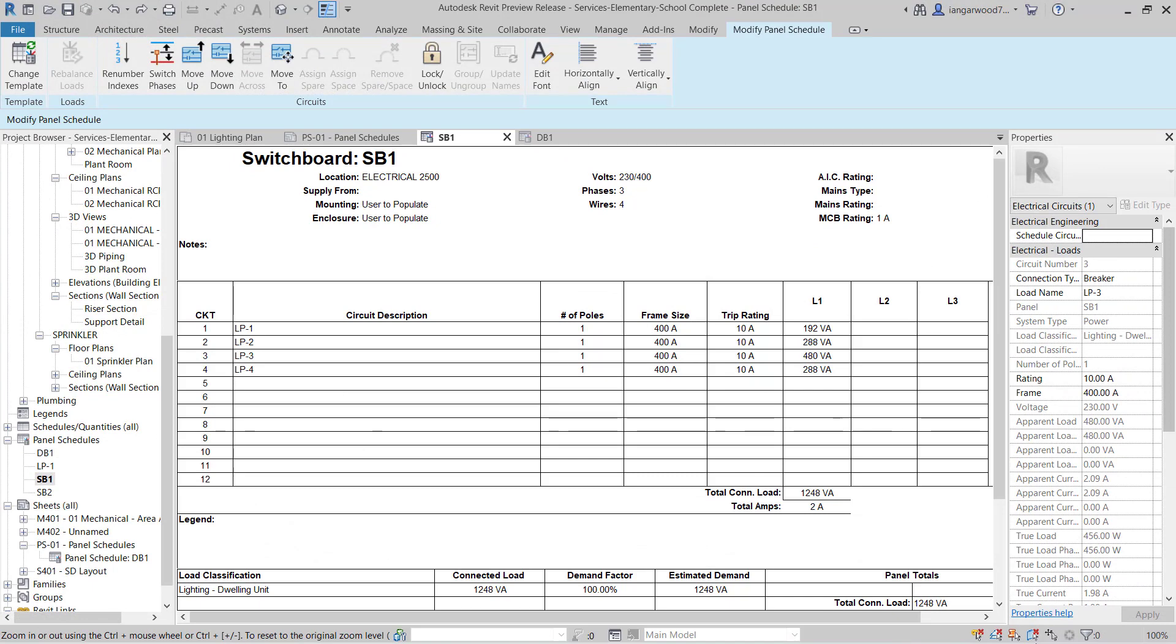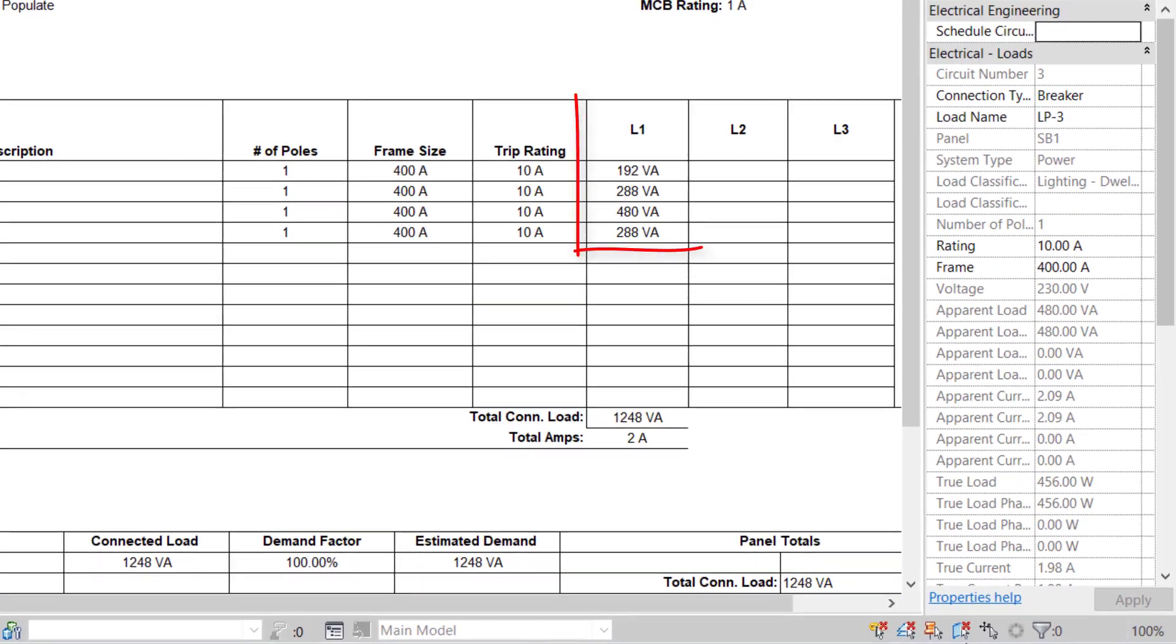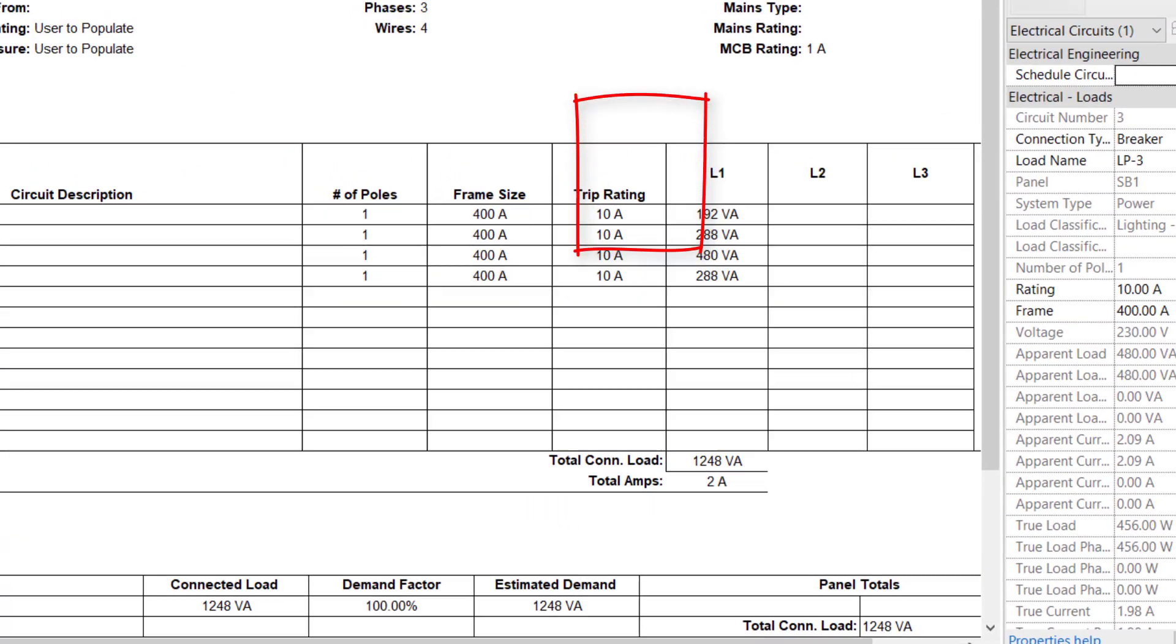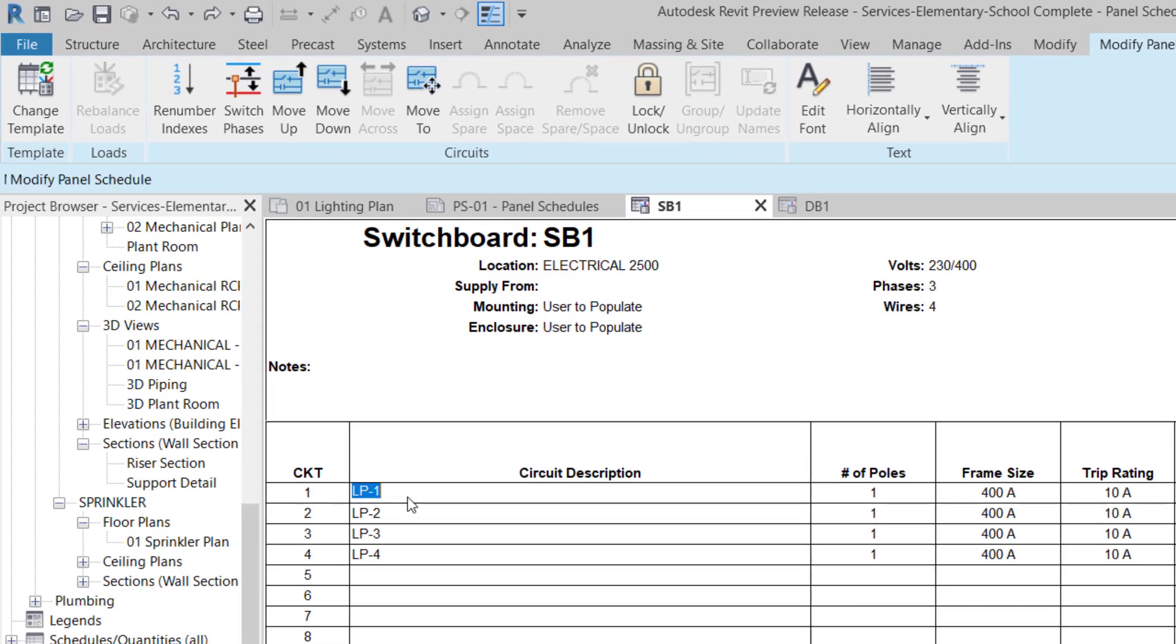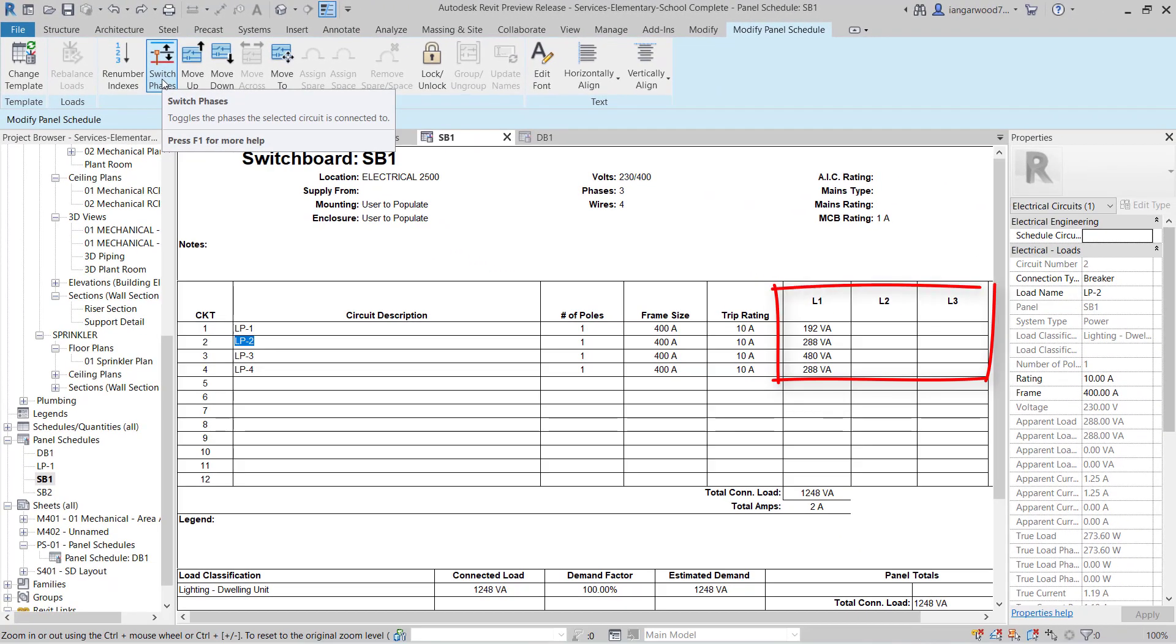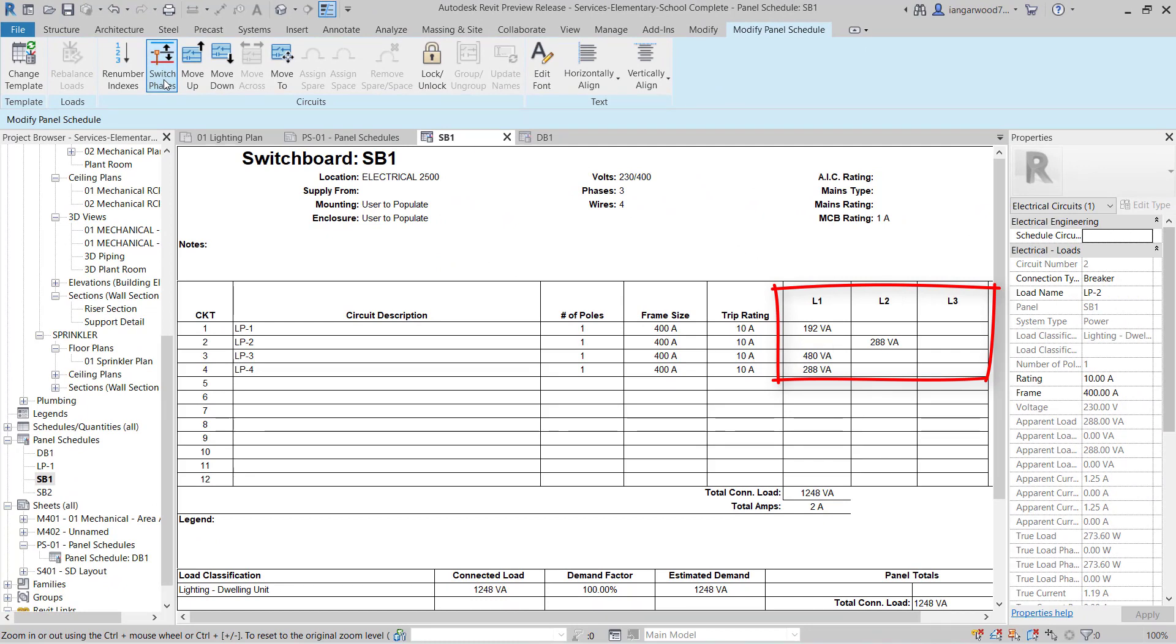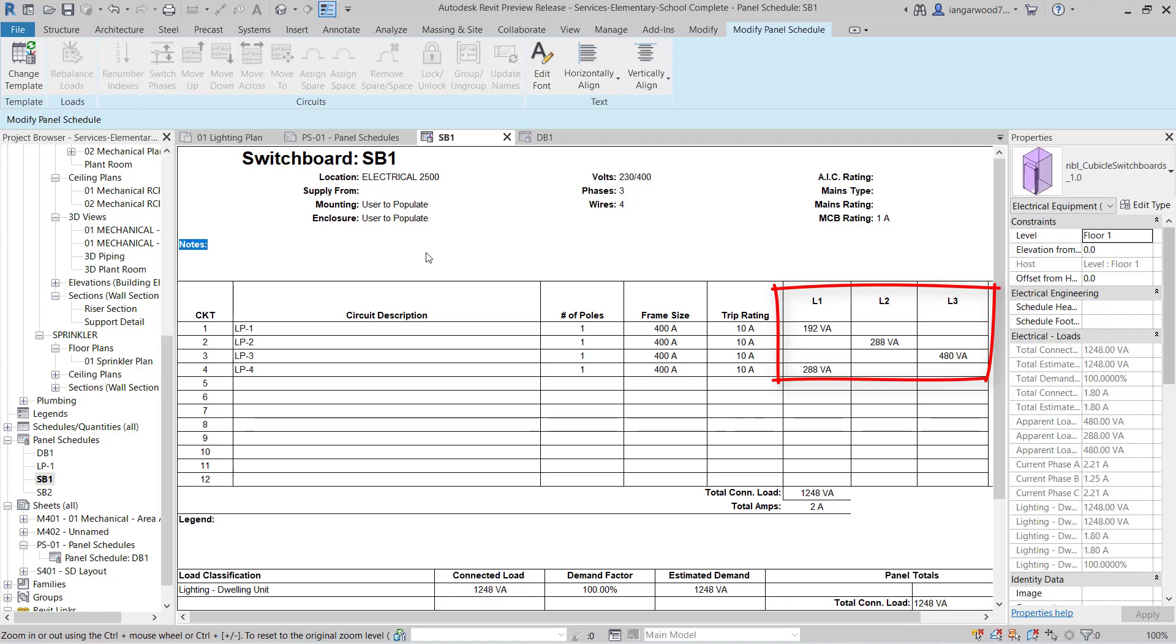Here we see the same arrangement in Revit MEP 2021 with a modified panel showing all three phases on the switchboard. For any single phase load connected to a switchboard, the new switch phase feature gives the option to move loads across phases and when used the results can be seen on the modified switchboard panel schedule.